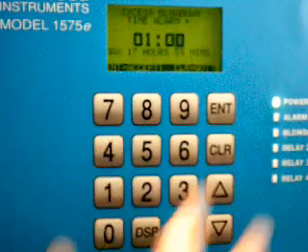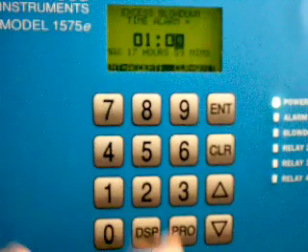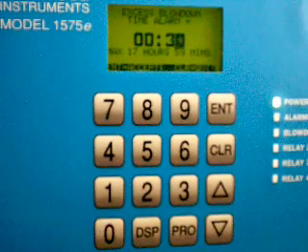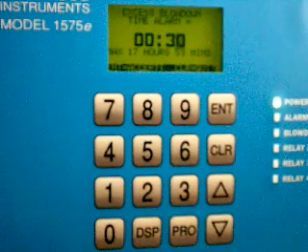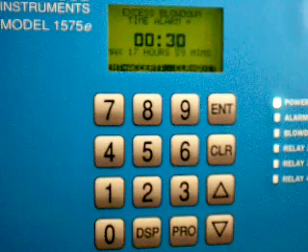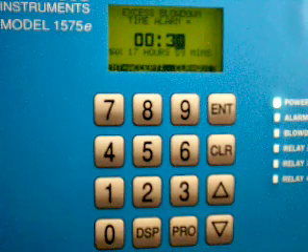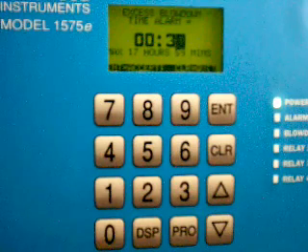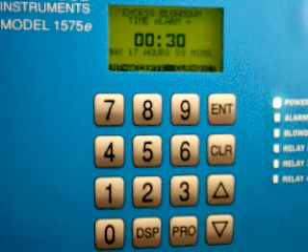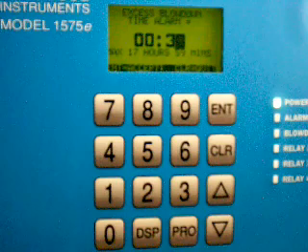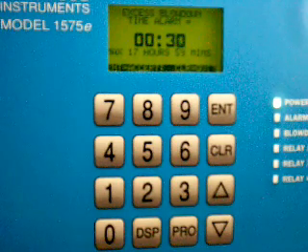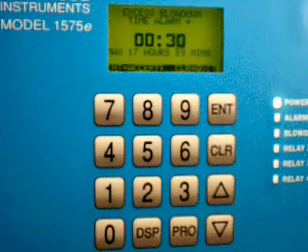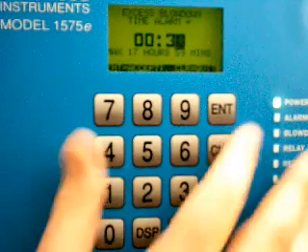Press Enter and it enters it. Now this is the alarm control — it's set for an hour, but let's say we set it for 30 minutes. What happens here is the blowdown doesn't shut off, but what it says is: normally I should blow down much faster, but if I take longer than 30 minutes, I want that alarm light to come on. For example, a solenoid valve may be stuck, so you want to know that you're taking an extremely long time to reach your set point. It does not affect the operation of the relay — the relay is going to continue to operate — but it does let you know that an alarm condition occurred. Press Enter to enter it.